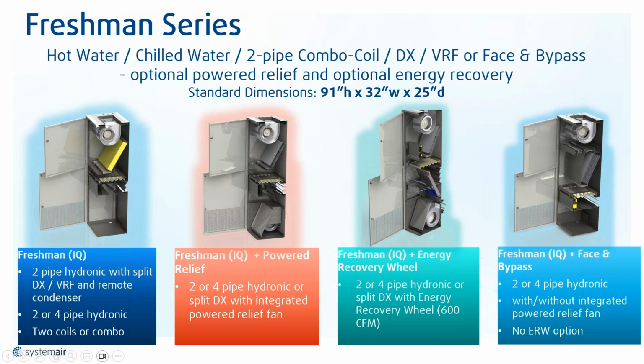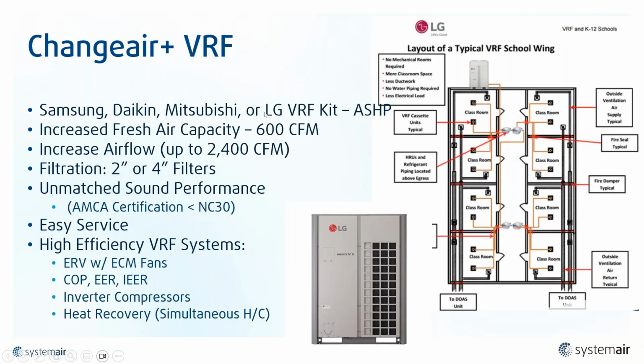So this one is flexible because with this unit, we can add VRF components to it. If you give us your VRF components, whether it's Samsung, Daikin, Mitsubishi, LG, we like to call ourselves VRF agnostic, we can help mount the EEV kits or the LEV kits. You can mount your comm boxes into our unit, and then you have a really powerful solution because you have NC30, that AMCA certified air handling unit or AMCA certified classroom unit, plus the environmental or energy efficiency of the condensers of the VRF. So you get the best of both worlds. And then all that needs to be done on site is, obviously, wire the unit and bring the refrigerant lines into the unit as well, because we would have installed the comm box and EEV kits. Depending on the model of the manufacturer, we can include things such as the energy recovery wheel if you need it, etc.